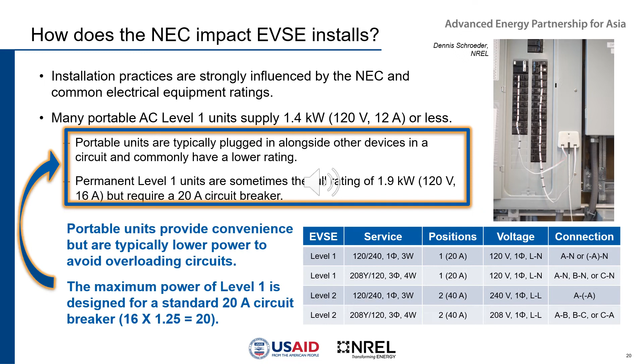The most common level 2 power options are also influenced by common equipment options. Although the standard permits devices to operate at a maximum of 80 amps, this would require a 100 amp circuit breaker, which is not very common. The most common option is a 32 amp level 2 EVSE properly installed with a typical 40 amp circuit breaker.